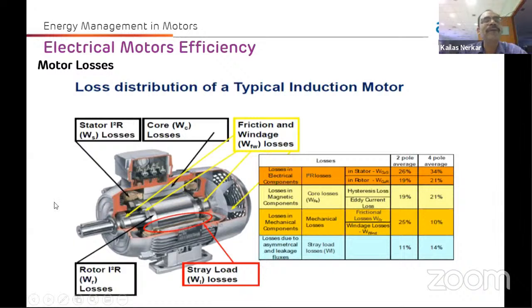I am trying to indicate that this is the stator I-squared-R loss. Here is the winding stator I-squared-R loss. Core losses are here, and here are the friction and windage losses, in the bearing or shaft bearing area, and the fan area. Then there are stray losses due to leakage flux, and rotor I-squared-R losses. These are the losses, shown here in tabular form.